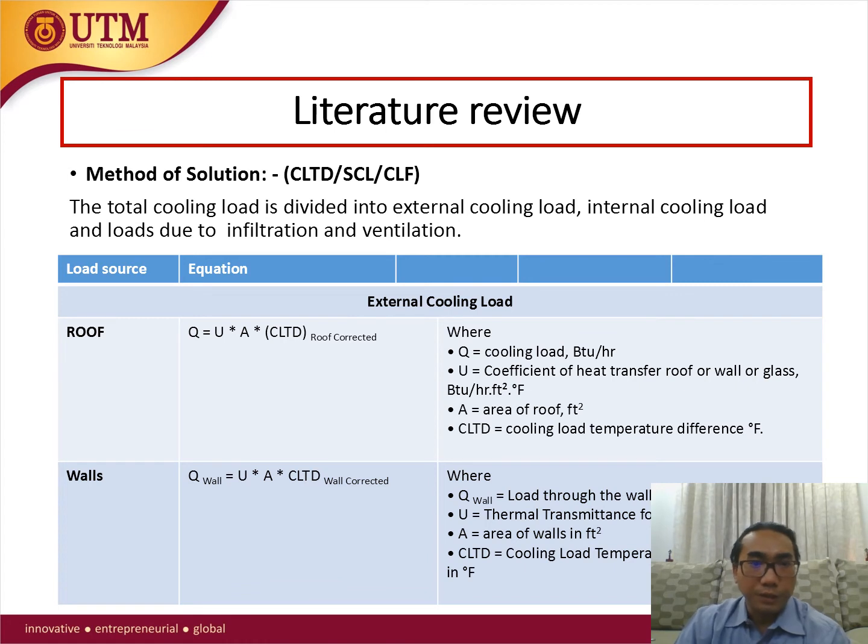Method of solution: CLTD, SCL, CLF. The total cooling load is divided into external load, internal cooling load, and loads due to infiltration and ventilation. The external load consists of heat transfer by conduction through the building walls, roof, floor, door, etc., and heat transfer by radiation through fenestration such as windows and skylights. All these are sensible heat transfers.